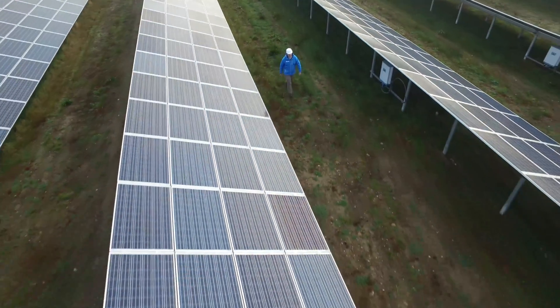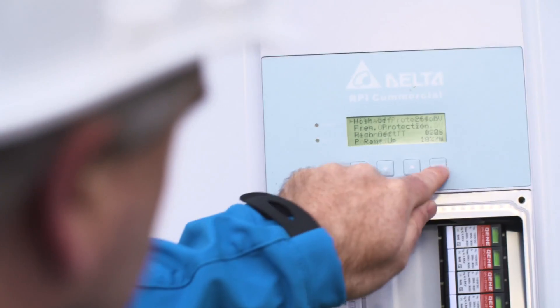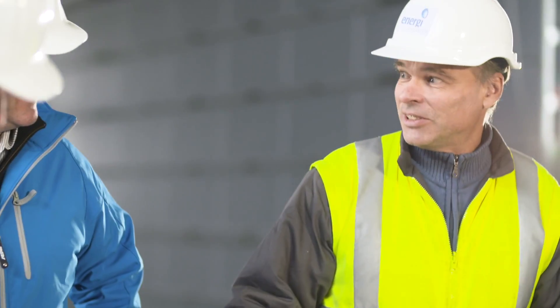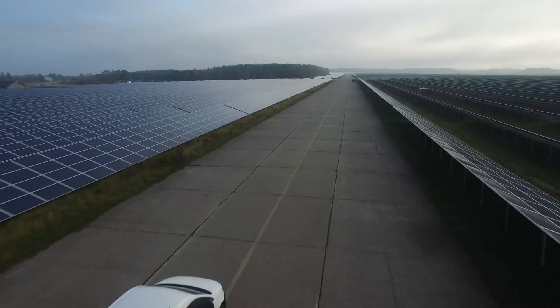The DC side is connected directly on the mounting structure. During the installation, we had a lot of help from the service team with software updates and the final commissioning for the end customer. Also afterwards, we used the service team from Delta to investigate other problems in the park — not directly related to the Delta inverters, but coming from the rest of the solar park, which is mainly due to the extremely high overpowering that we're running here.